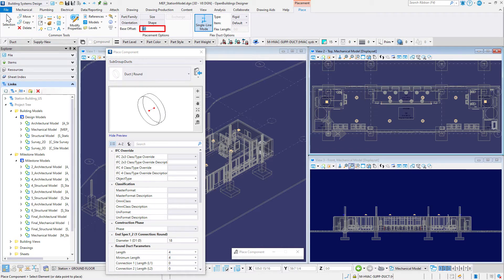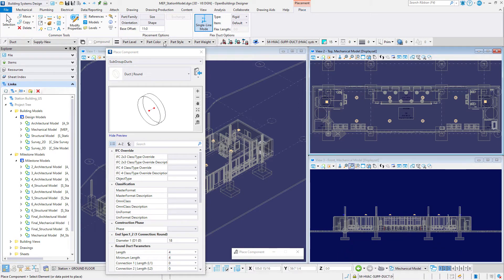Set the base offset to 11 feet or 3,500 millimeters. This is enabled when a floor is selected in the floor manager as a reference plane. It sets the z-axis distance between the elevation of the active floor and the centerline elevation of the ductwork being placed, thereby allowing you to route the ductwork relative to the active floor.